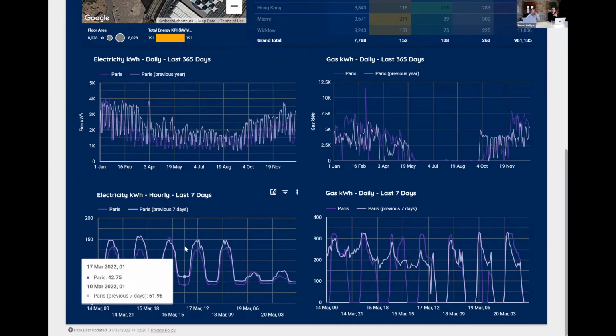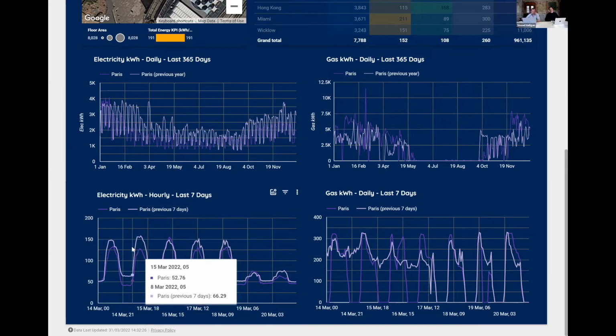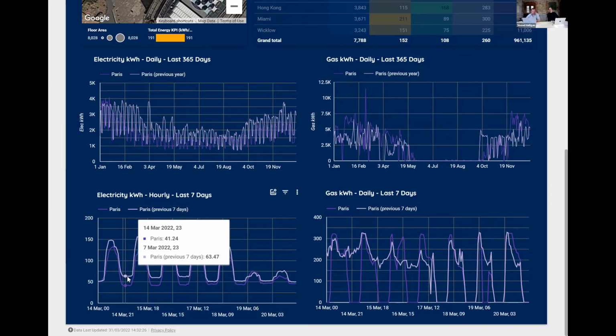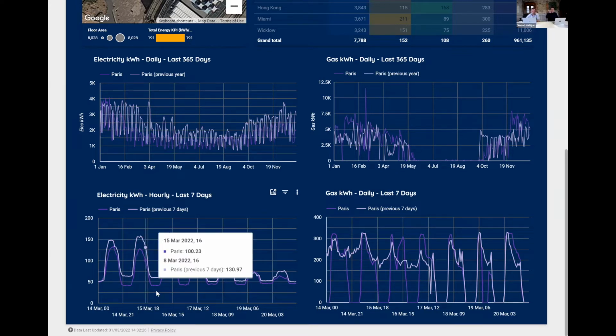What you can see here is this week, during the nighttime periods, these troughs here on that graph, there are base loads of 41 kilowatts being achieved. But the previous week, during the exact same hour of the day, they're running at 63, so in excess of 20 kilowatts. So we know that the achievable baseload target here is 40 kilowatts.